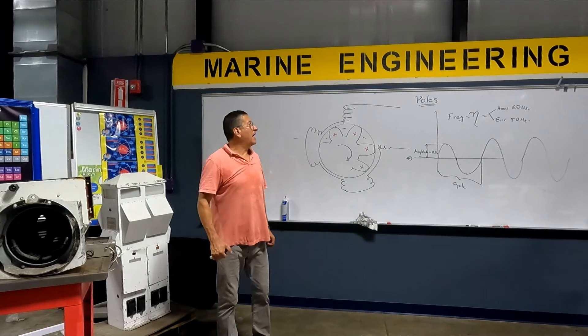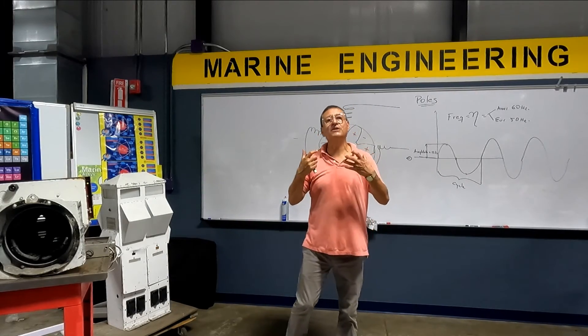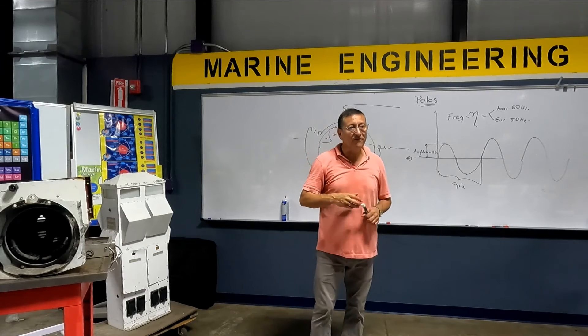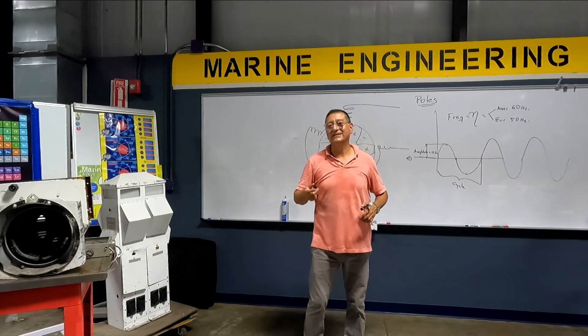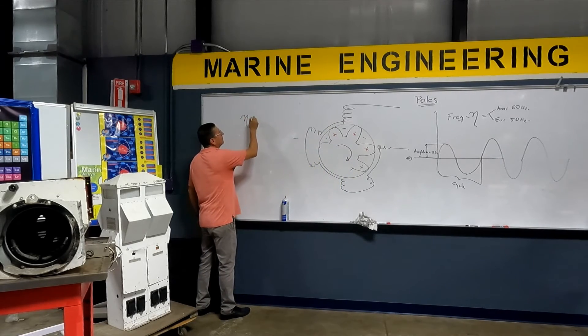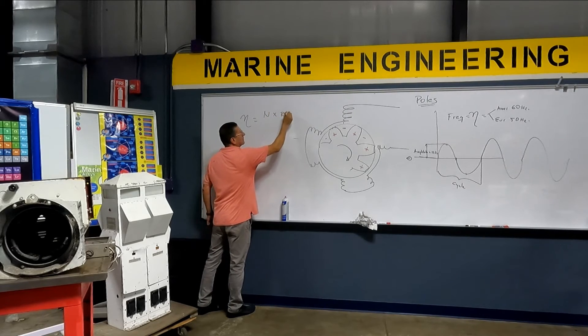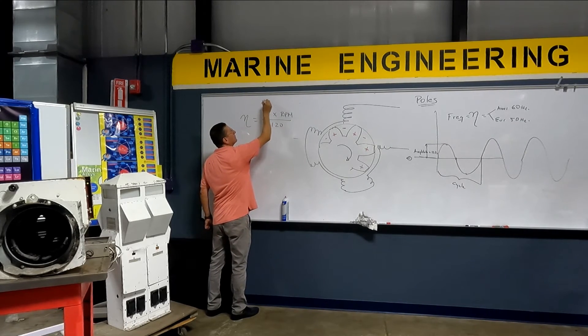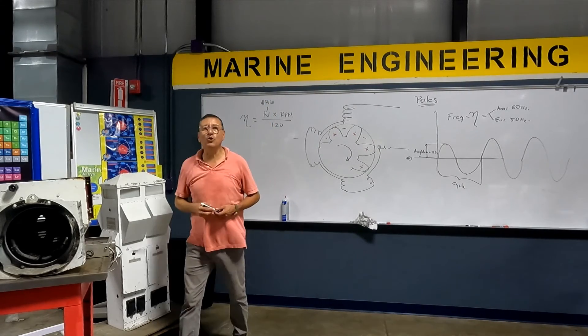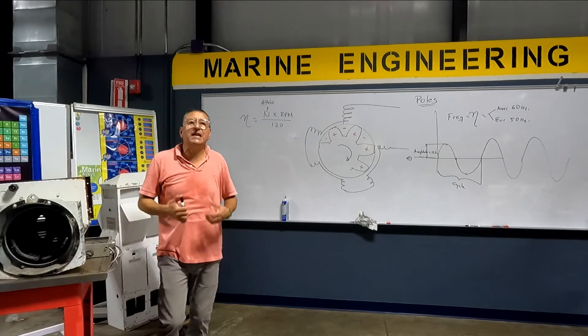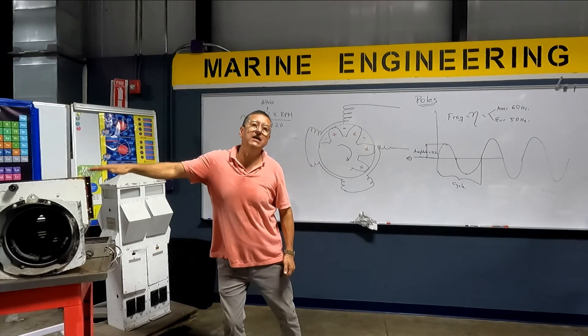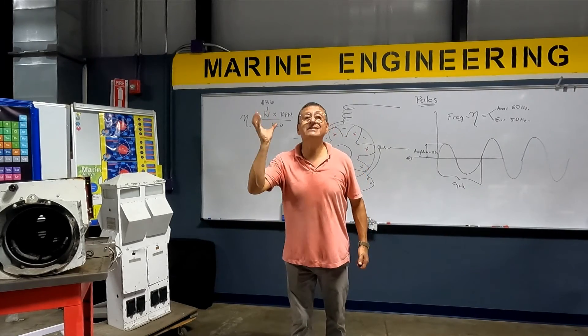Now let's understand the formula for frequency — it's the same formula used to calculate frequency produced by a propeller when spinning. The formula is: frequency equals the number of poles times the RPMs divided by 120. Let's calculate how many RPMs are needed in an American generator to produce 60 hertz.